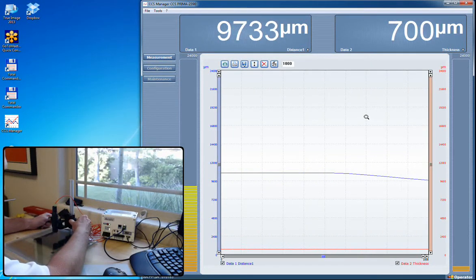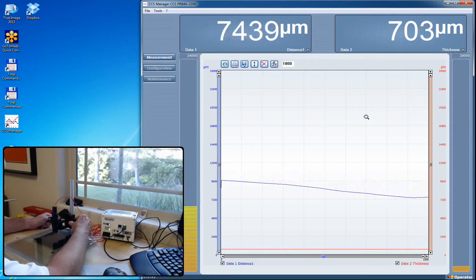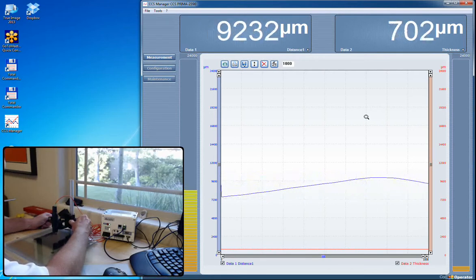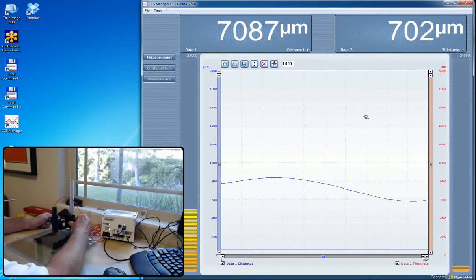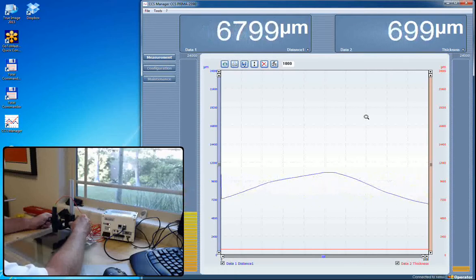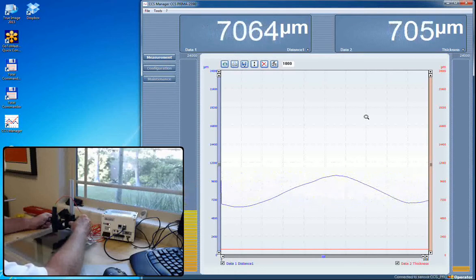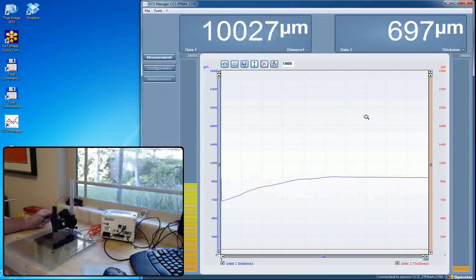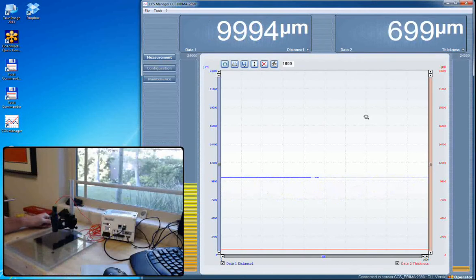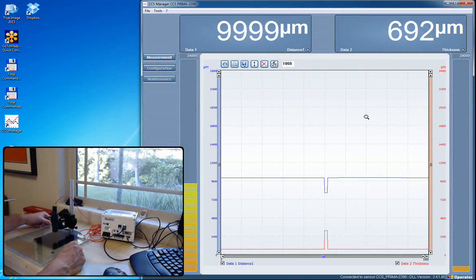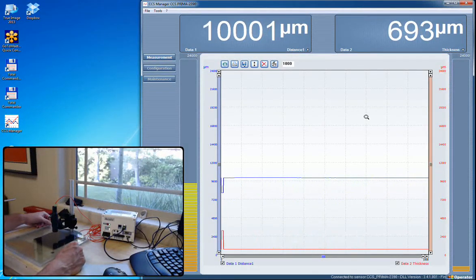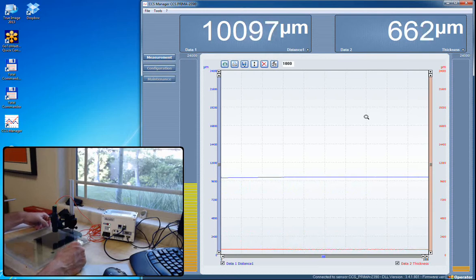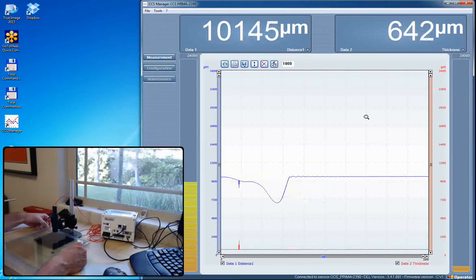As I move this you'll see the blue come down and that thickness is staying the same. What that shows is that we can determine where the front face is and it doesn't matter because we're still seeing the thickness. As we move this around you can see that we're getting thickness measurement readings on the surface very accurately at almost any point.